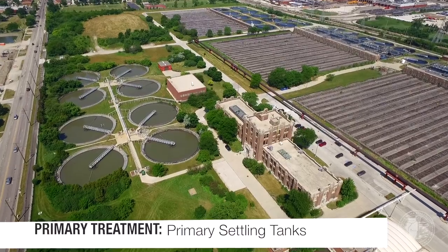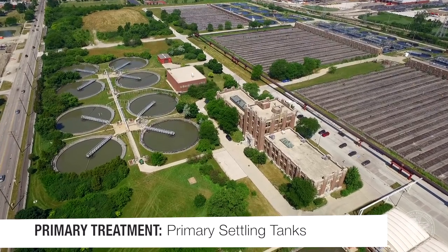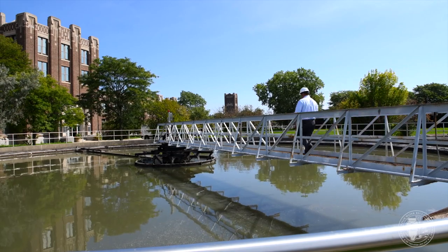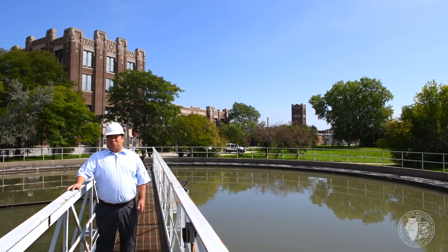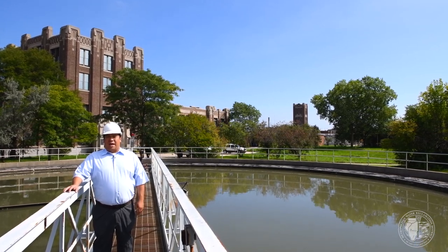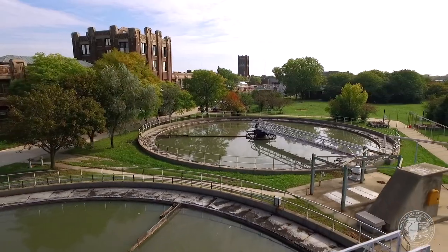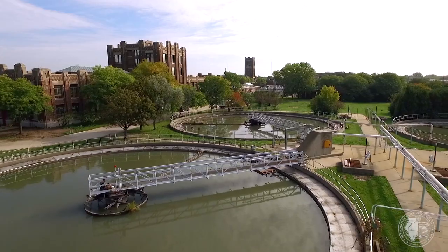The screened and degritted water flows into primary tanks. These basins hold approximately one million gallons and are about 15 feet deep. The water is held here for about two hours, during which heavy organic solids settle to the bottom. The cleaner water then leaves the primary settling tanks and moves on to step two: secondary treatment.